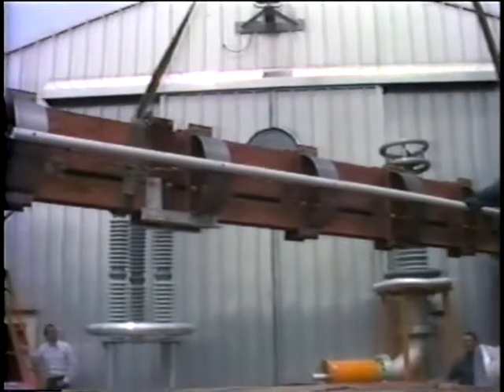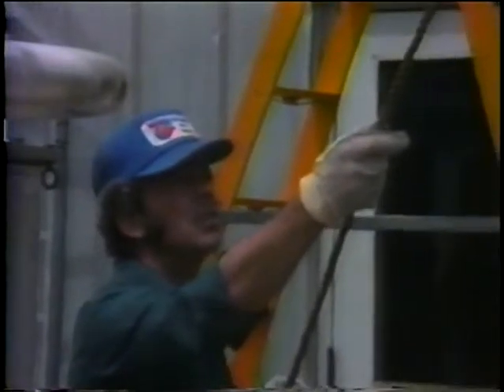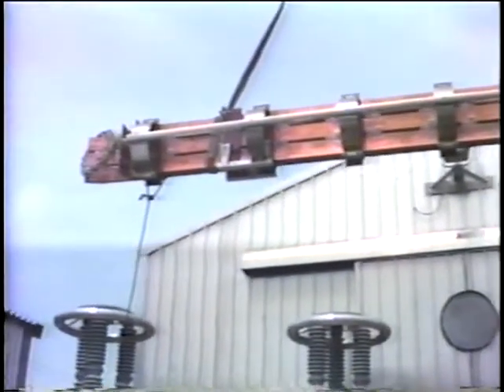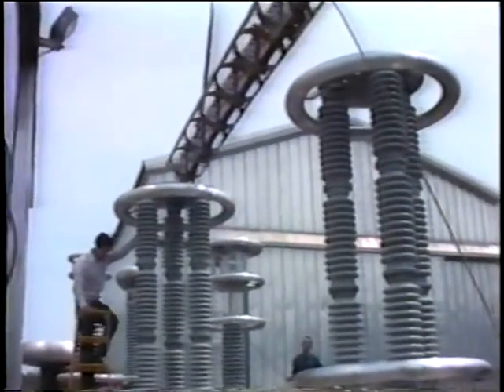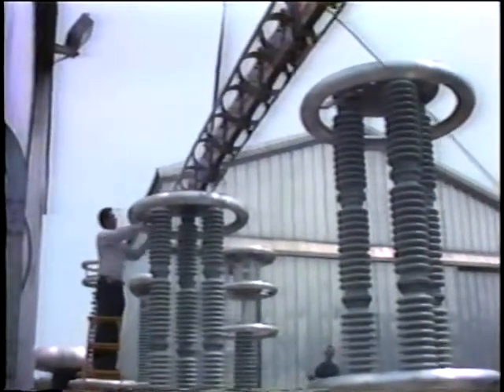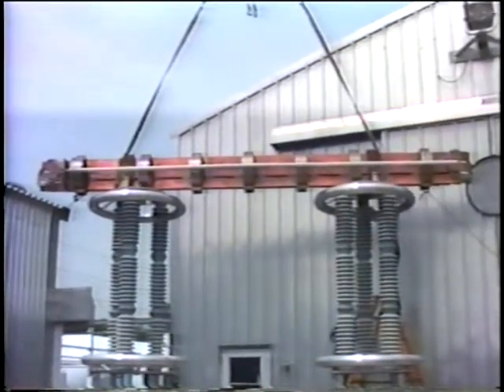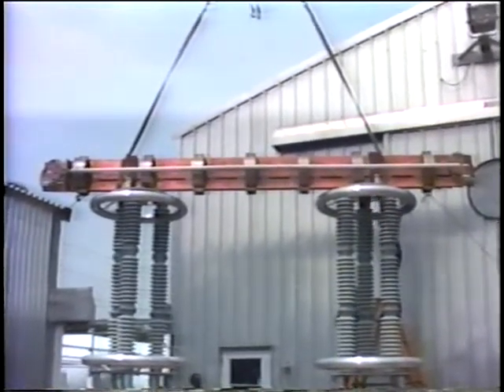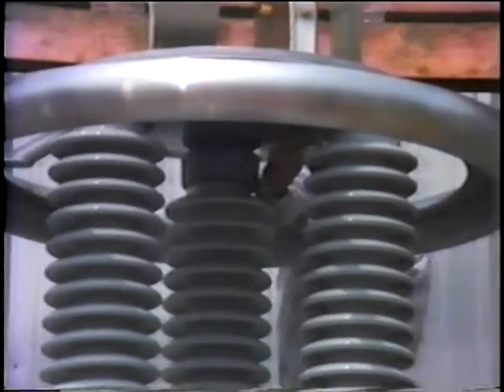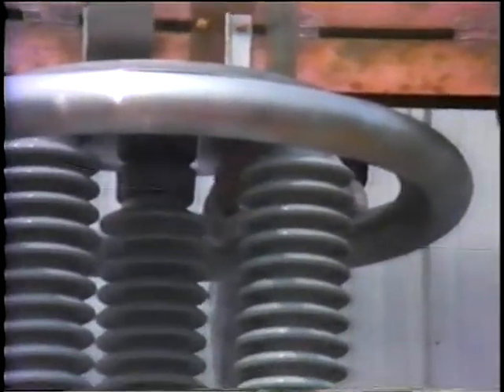Here, the copper bus bars which connect the power supplies to the west end terminations are being lifted into position on the insulated supporting stands. The size and weight of the bus bars, which carry the same current as the superconducting cables, emphasize the amazing current carrying ability of superconductors. The bus bars have a cross-sectional area about 400 times larger than the superconducting tapes forming the cable conductor. These were seen earlier as the thin metal strips which were formed to complete the cable ends.